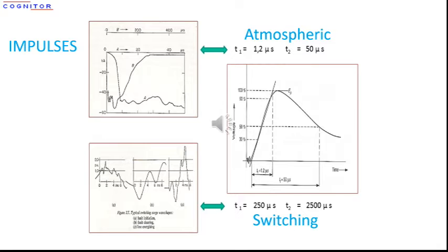And for the switching impulse, the representative wave is the so-called 250 by 2500 microseconds. This wave is also applied in testing for the so-called switching impulse tests.